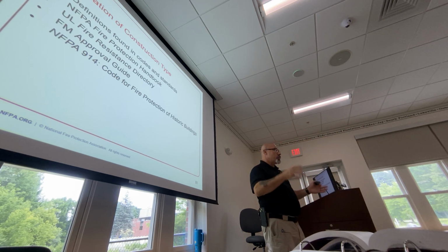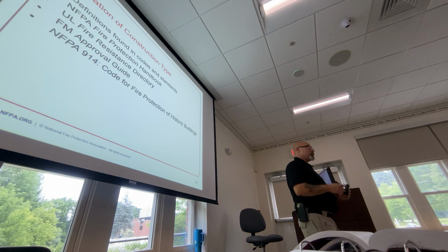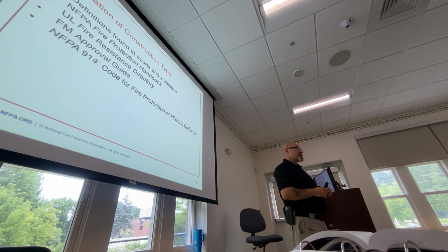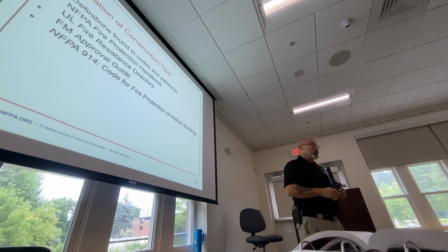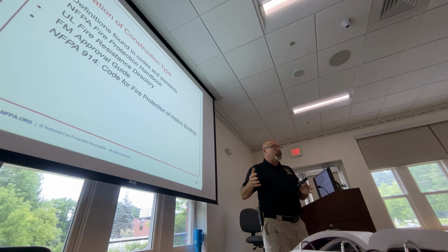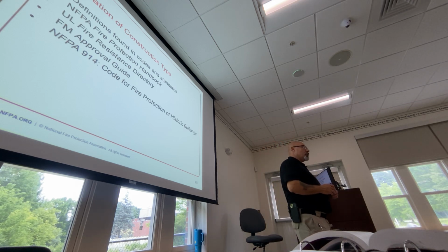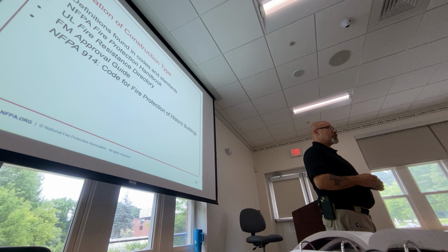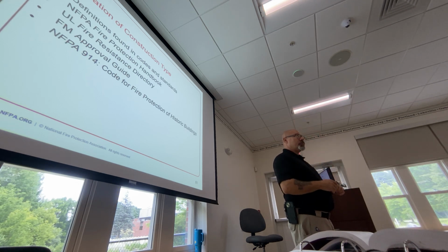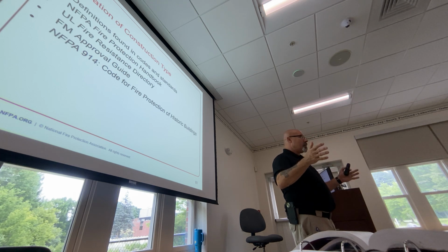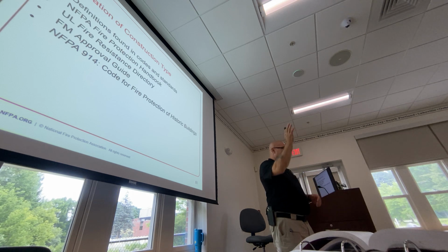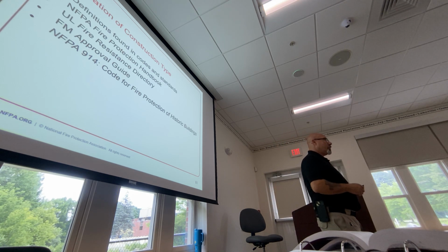And that roof structure, they wanted it to look pretty for this new hospital addition. It was designed as a heavy timber type construction, which was acceptable and met the requirements of the code. But when we went to do the inspection, the beams, columns, and supporting structure all met it, but for the roof they put just regular 3/4 plywood.